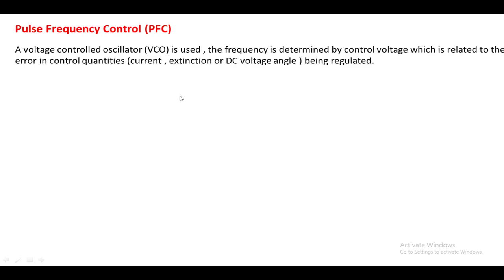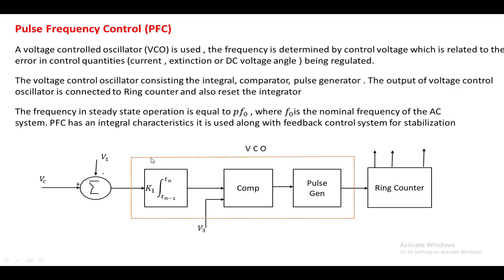In pulse frequency control, an oscillator is used consisting of an integrator, comparator, and pulse generator. The control voltage Vc is derived based upon the current, extinction angle, and DC voltage angle. It only determines the frequency of the pulses. The output of the voltage-controlled oscillator feeds a ring counter which generates pulses to the valve and also resets the integrator. Pulse frequency control has an integral characteristic and is used along with a feedback control system for stabilization.